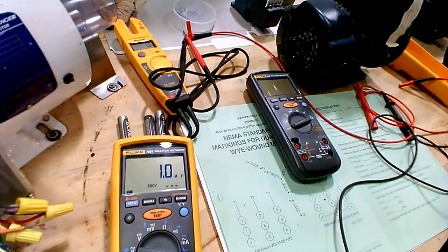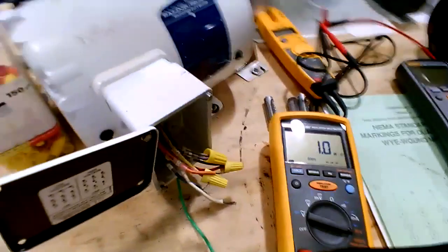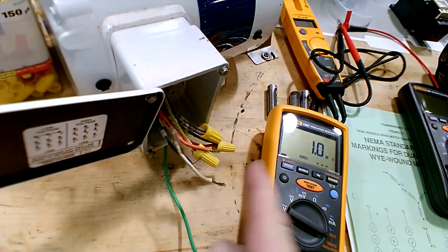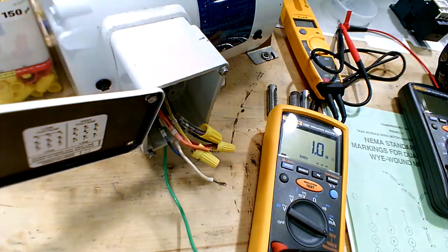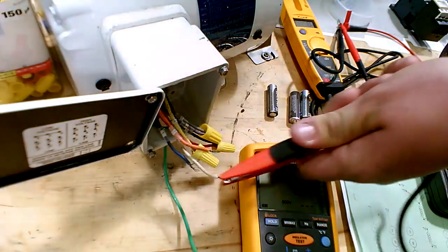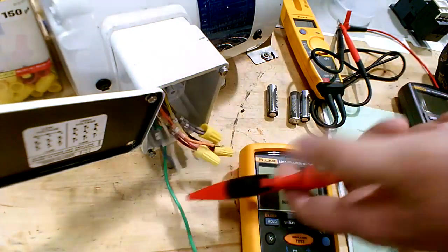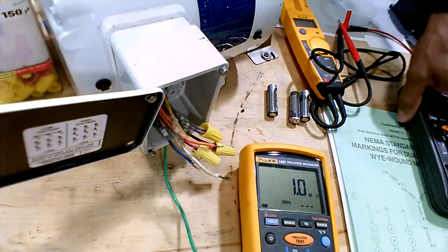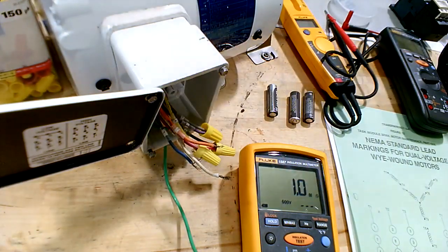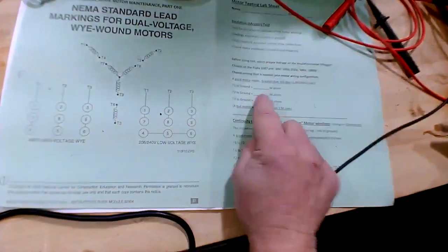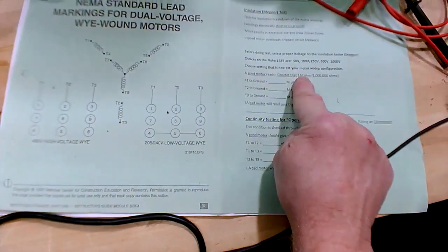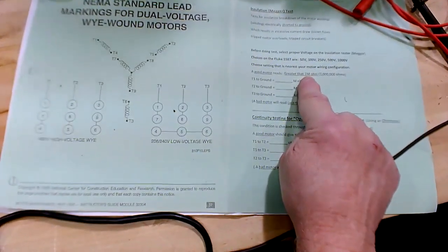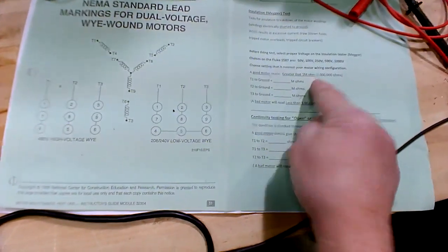And so we're going to go to this motor here. This is a good motor. You're going to check from each lead to ground and hit the button. And here's what your limit would be, your recommended number. By the lab sheet, it says a good motor reads greater than 1 megohm from each leg to ground. So if you're above 1 megohm, you're fine. Less than 1 megohm, you're bad.